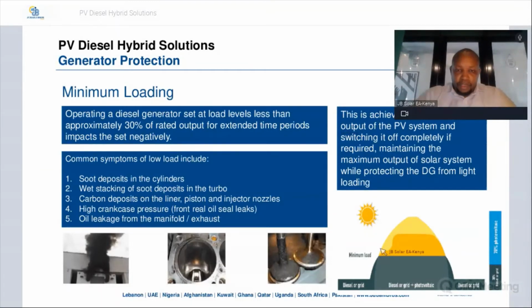Since you have high PV, and you want to make sure that your generator is performing optimally, the controller will reduce the output of the PV system or also switch it off entirely to make sure that your generator is operating above the minimum load rating. So the controller can switch off or reduce the output of the PV system so that you can maximize the output of the generator and protect it, so that you're not operating below the minimum rated load.